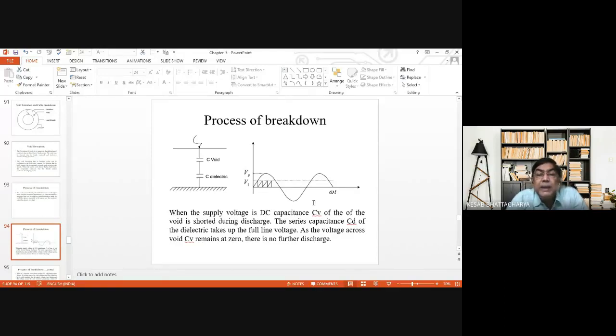Now, in the case of AC application, there is a chance of repeated flashover. I should not say flashover, the correct term is repeated discharge or repeated breakdown. But in the case of DC, there will be only one breakdown because in DC, the magnitude of the voltage is not changing, nor does the dV/dt increase. There may be one breakdown or one ionization of the air bubble, but the voltage magnitude is held constant at that value, so the dV/dt will not change. As a result, in DC, there will be a single breakdown. Is the point clear?